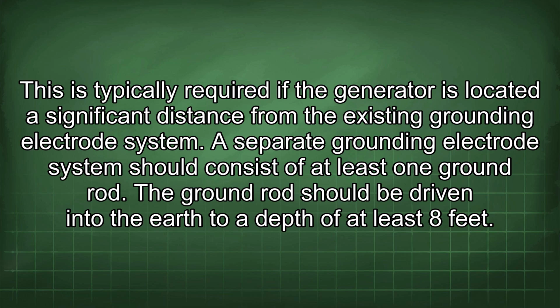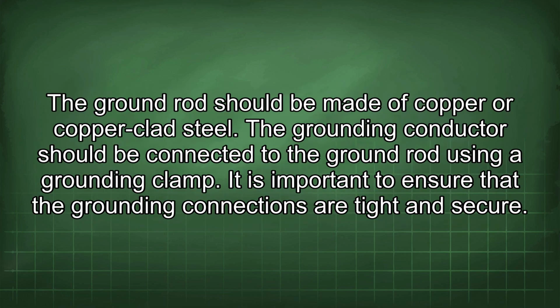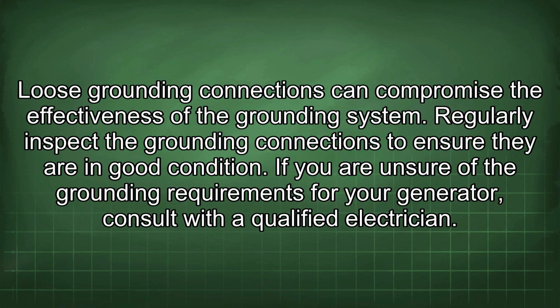A separate grounding electrode system should consist of at least one ground rod. The ground rod should be driven into the earth to a depth of at least 8 feet. The ground rod should be made of copper or copper-clad steel. The grounding conductor should be connected to the ground rod using a grounding clamp. It is important to ensure that the grounding connections are tight and secure. Loose grounding connections can compromise the effectiveness of the grounding system. Regularly inspect the grounding connections to ensure they are in good condition.